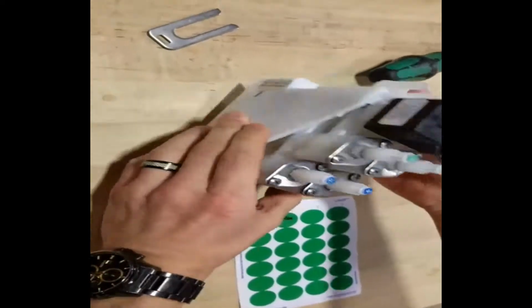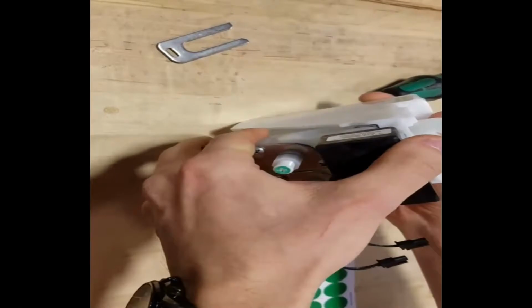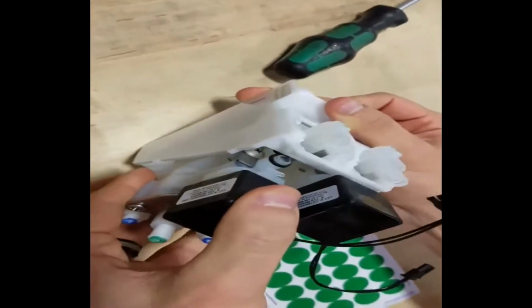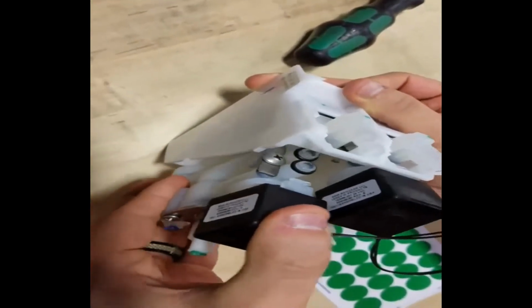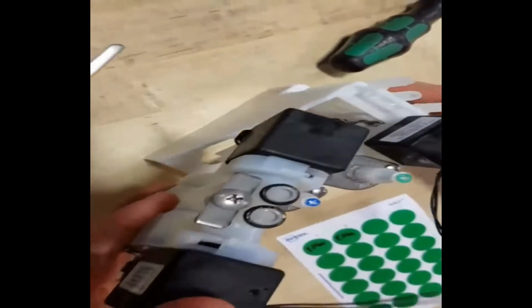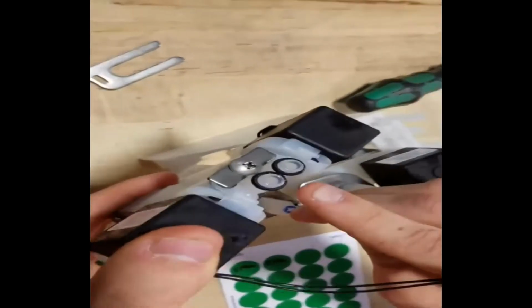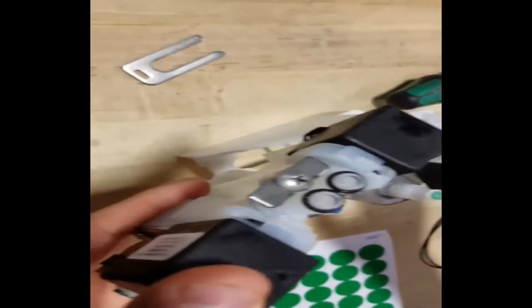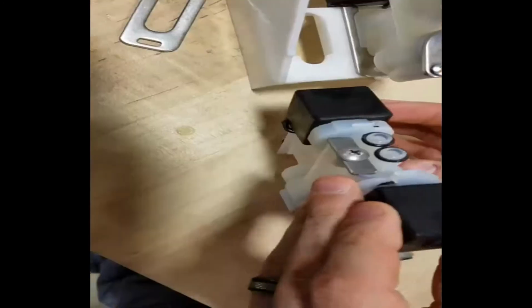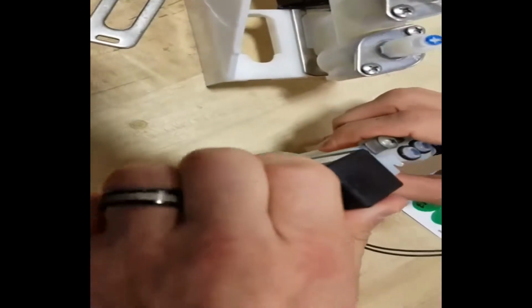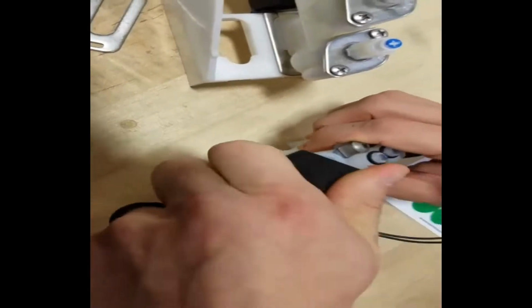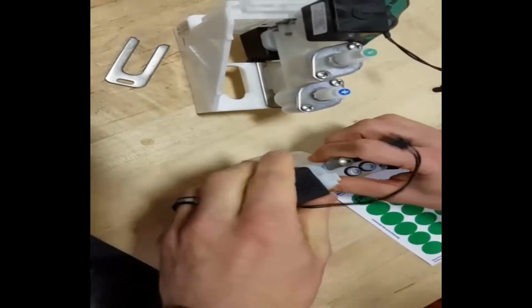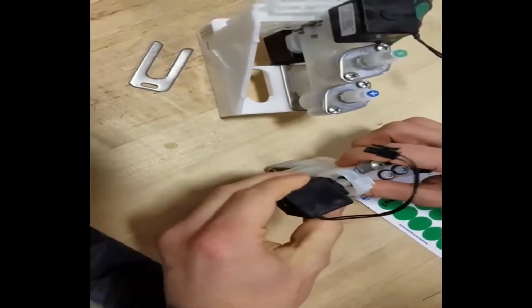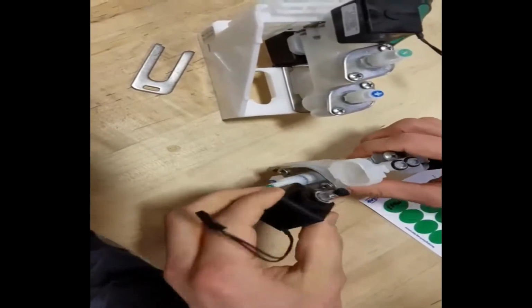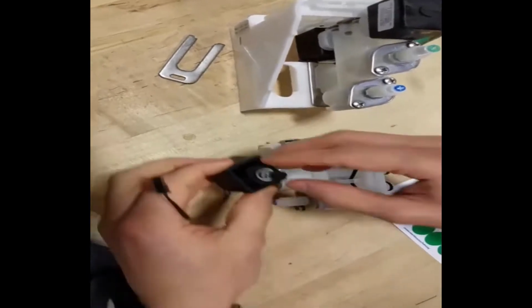You want to remove the module off the valve cradle. Just pull it out at an angle. You want to make sure those O-rings are always with the valve module. Do not lose those O-rings. And to replace the solenoid, all you're going to be doing is just twisting counterclockwise, and that disengages the solenoid off the valve module.